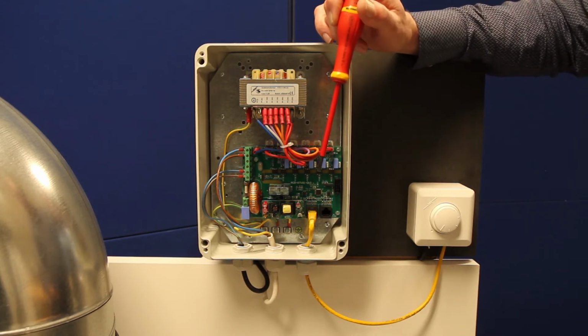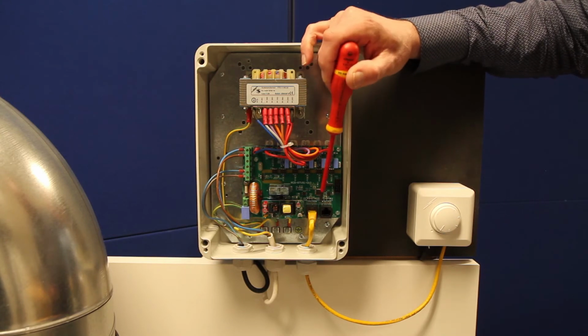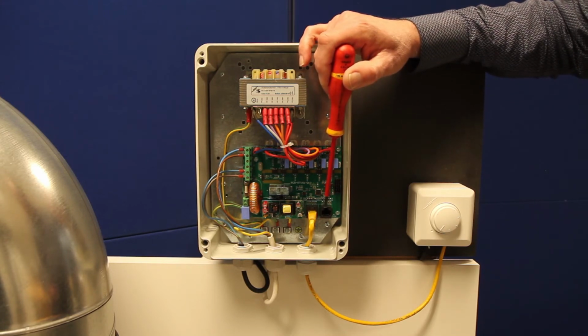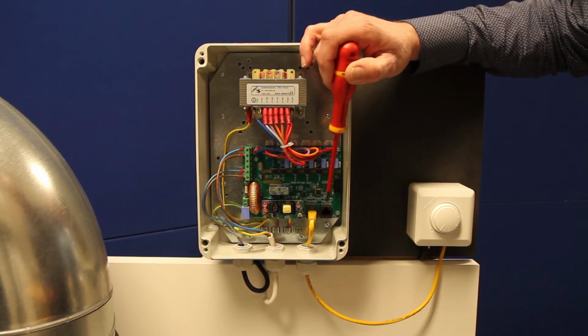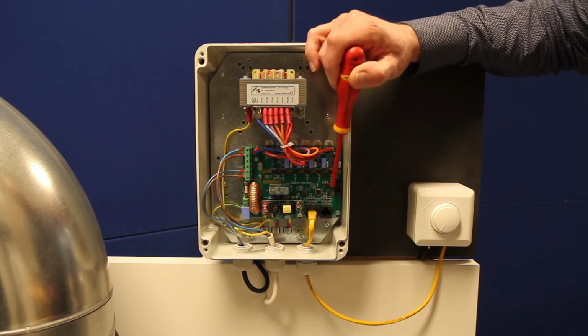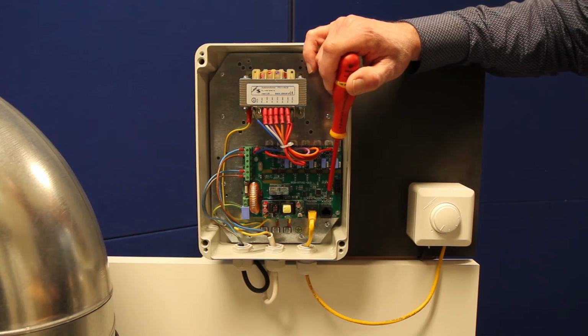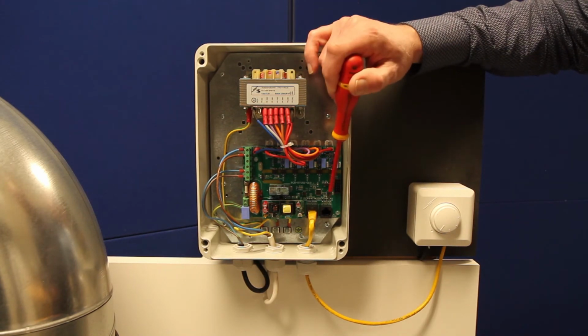If your sensor is a multifunction sensor that records several measured values, then you need to determine in the Modbus registers whether the device should take CO2, relative humidity, temperature or any other measured value into account. On the right RJ45, you can connect a Centera gateway or a building management system. If you connect a Centera gateway, you can manage the device through the internet.